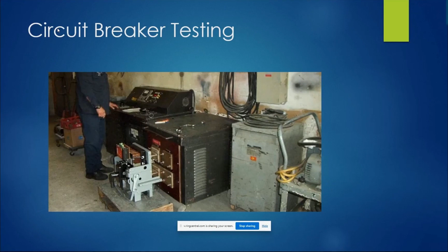So July 4th or Christmas holidays, when y'all have a scheduled shutdown or long period shutdown, you'll call in one of our partners, such as Power Solutions or Instel, and one of those guys will come in and do your circuit breaker testing for you. But we can help facilitate that. We have business partners that help do this kind of testing, and we are happy to make those connections for you guys. And what kind of breakers are we talking about? We're talking about breakers greater than 800 amps. 800 amps and larger need this kind of testing, and at minimum, on the standard classification, it says 60 months.